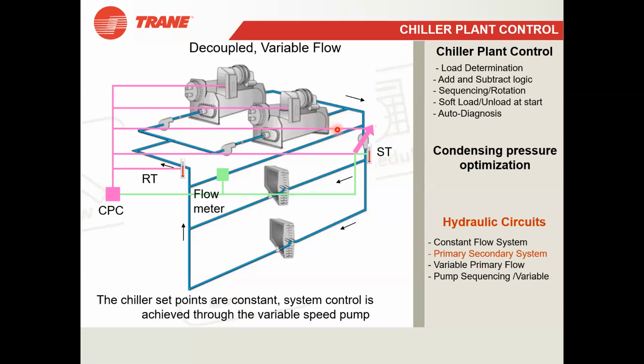So where will the other 50% go? There is a bypass line. So that will go through this bypass line to the main line again. So excess water, okay. Because secondary is now throwing 50%, you are getting lesser cooling, whatever cooling you want to maintain for lesser occupancy, that you are getting. But the secondary pump load has reduced, right? So when the speed has been reduced, the load has been reduced. If it is reduced by 20%, actually the energy saving will be 50%. So that way, you are saving your energy very much.